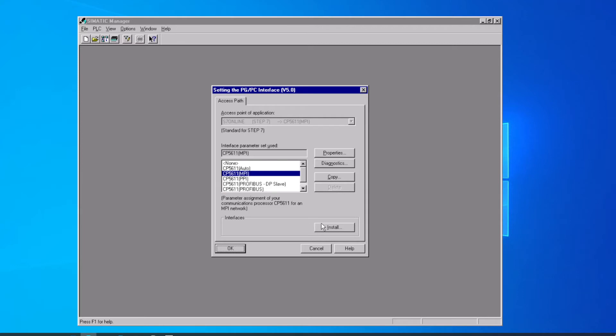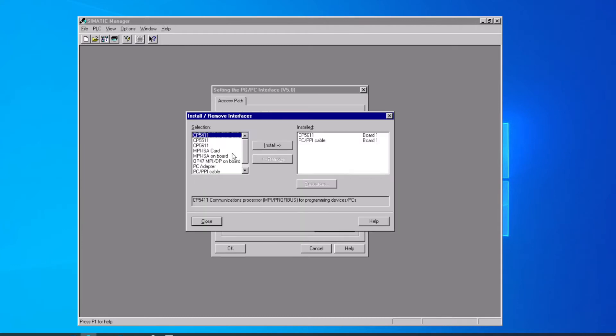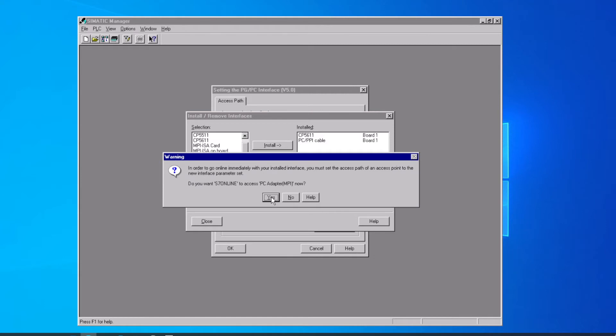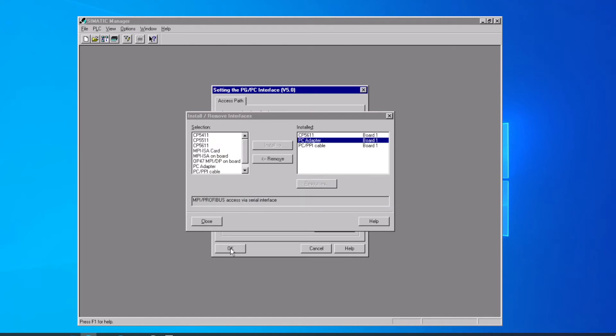Let's go ahead and install the PC adapter cable, which takes the serial port, just a regular RS-232 port, and adapts it over to the MPI network. We select that from our selection area, click Install. You see that comes up first and offers to set the S7 Online communication path to that new device we're installing. We say yes, that's okay, and then close.